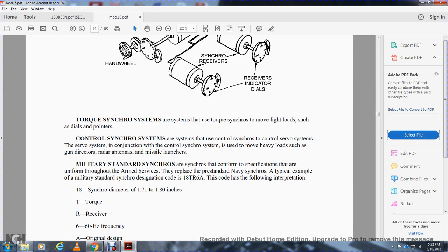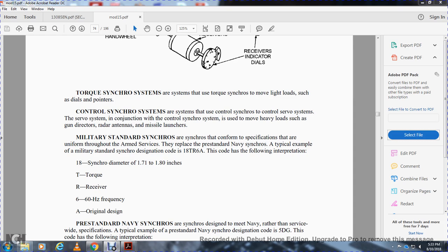Military standard synchros conform to specifications that are uniform throughout the armed services. A typical example of the military standard synchro designation code is 18TR6A. The code is interpreted as follows: 18 is the synchro diameter (1.71 to 1.80 inches), T for torque, R for receiver, 6 for 60 hertz frequency, A for original standard design.